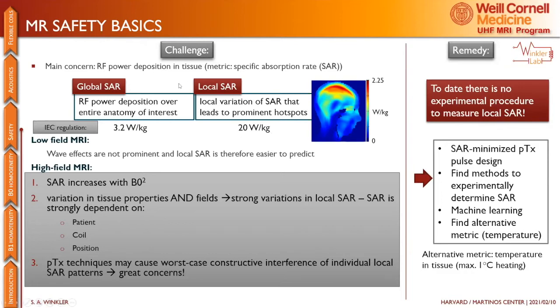So there are two main metrics. The first one is the global SAR. That would be the RF power deposition over the entire anatomy of interest. That one's actually easy to measure. You can just measure the reflected power and you get a sense of this global SAR. But what's really a problem at these higher fields is the local SAR, because we have local variation of SAR that comes from the wavelength effects, right? In the same way we had the maxima and minima for the B1, the RF field, we have maxima and minima for the SAR field as well. And you can see in this little image here that, without realizing, you could cook someone's tiny little area of the brain here and really cause problems.